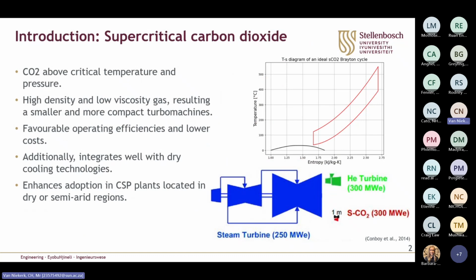Supercritical carbon dioxide is effectively CO2 above its critical temperature and pressure, well into the superheated region above the vapor dome, where the CO2 has the density of a liquid and the viscosity of a gas. These favorable thermodynamic properties allow the turbomachinery components of this power cycle to be designed with a much smaller footprint in comparison to a steam turbine drivetrain.